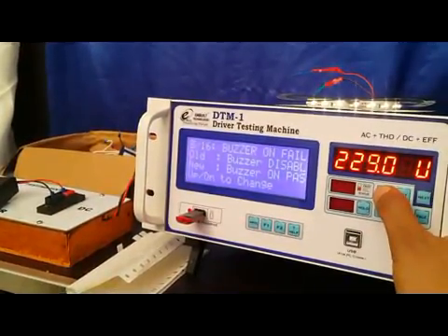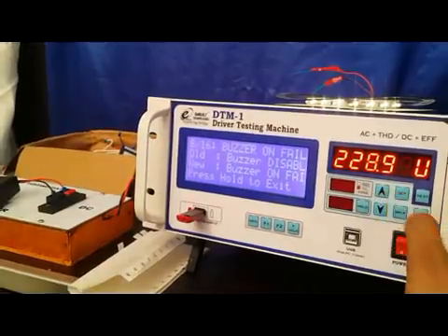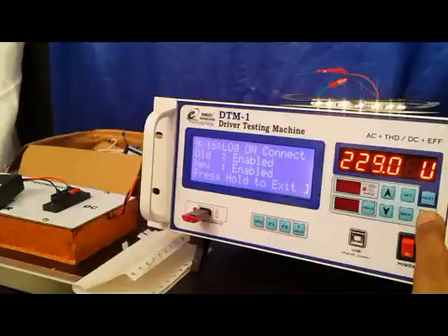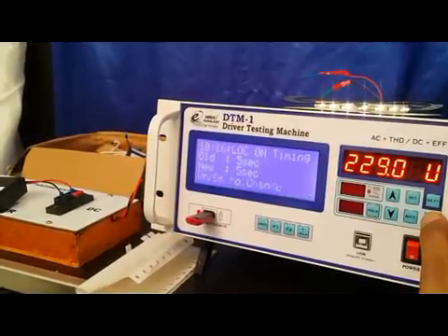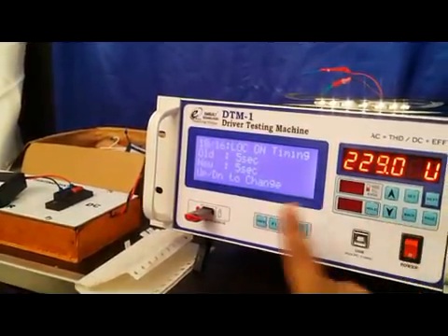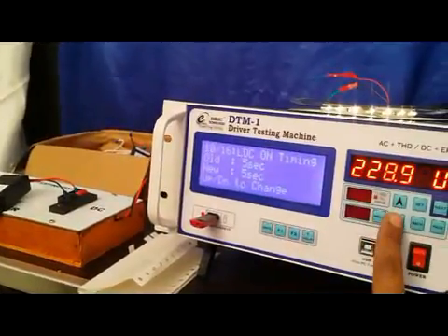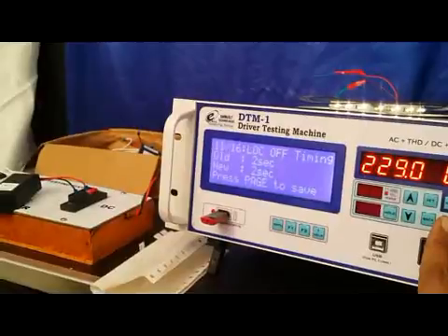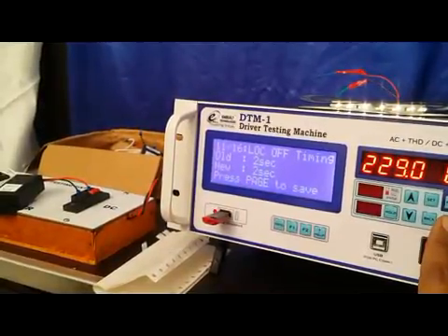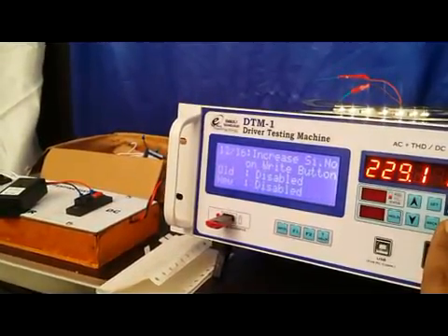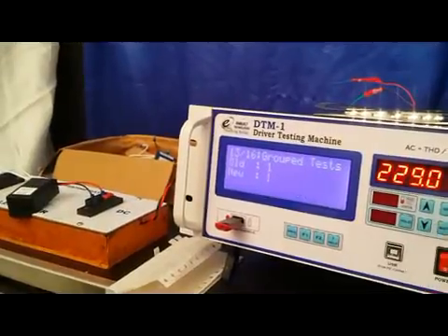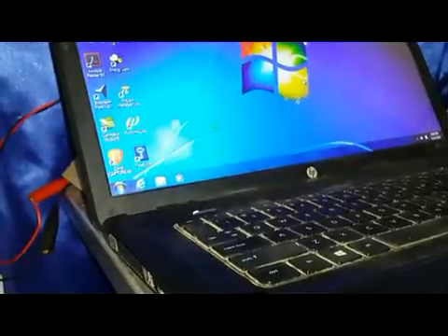Now we have gone into the settings menu and we have seen the model which is selected and whether the buzzer is disabled or enabled, and log-on connect is enabled, so that's why the serial number was incremented. Log-on timing, LOG ON timing, that is after how many seconds this saving is done, and off timing can be set here.